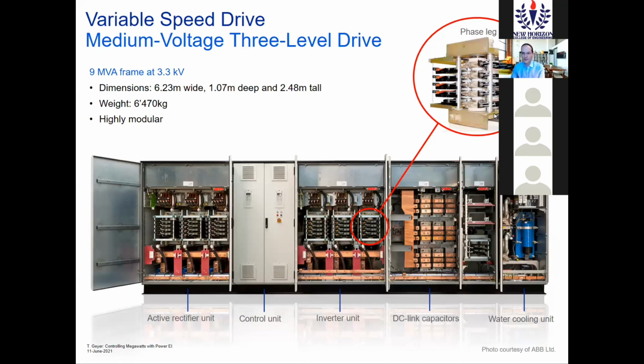And these devices are water cooled. You see here the water pipes. And this is required because they get extremely, very, very quickly hot. So one needs to actively pump quite a bit of water through them, deionized water, to remove the heat.